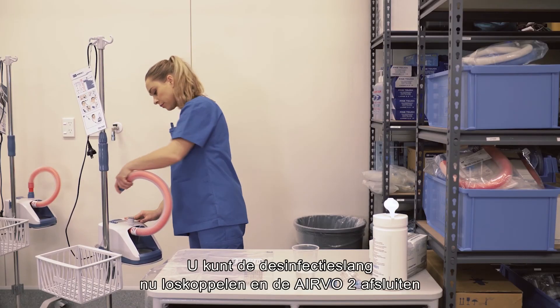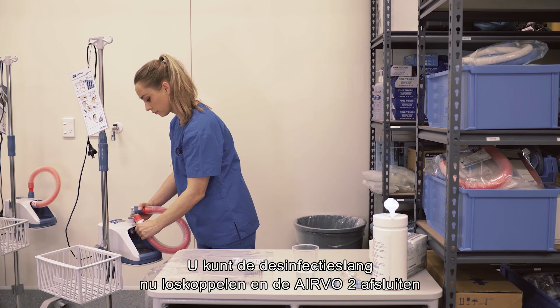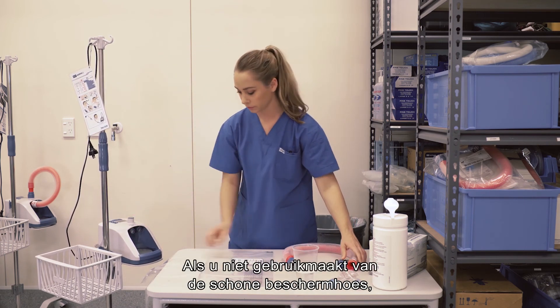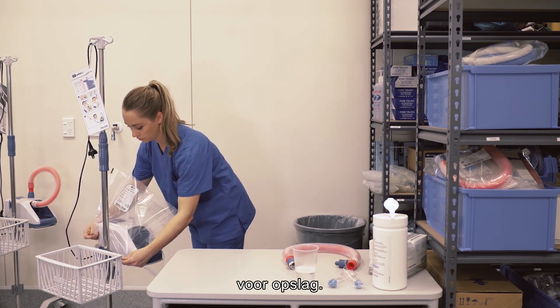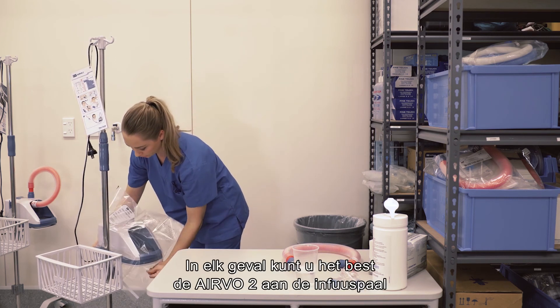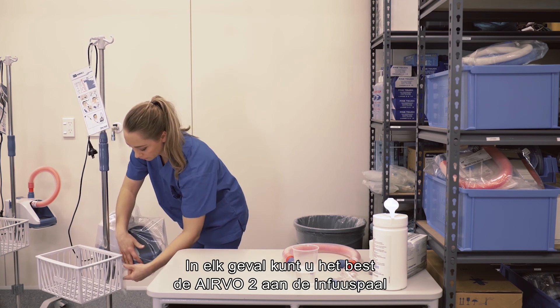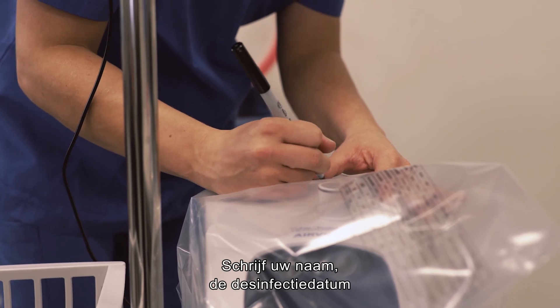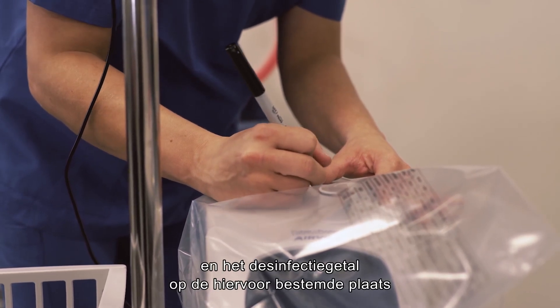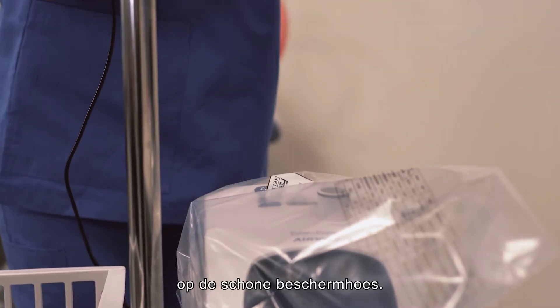You can remove the disinfection tube at this stage and seal the AIRVO 2 with a clean storage cover. If you are not using the clean storage cover, you may prefer to leave the disinfection tube in place for storage. In either case, it is best to leave the AIRVO 2 on the stand to protect it from bumps and knocks. Write your name, the disinfection date and the disinfection number on the space provided on the clean storage cover.